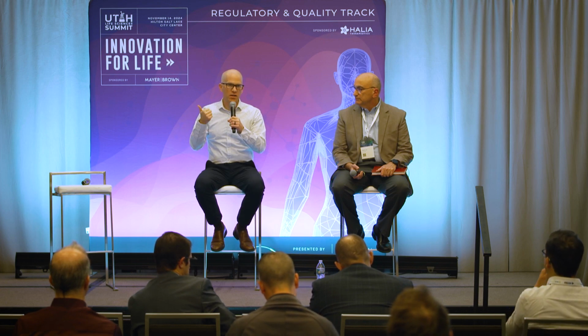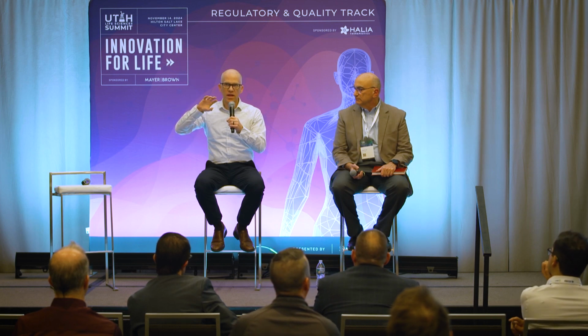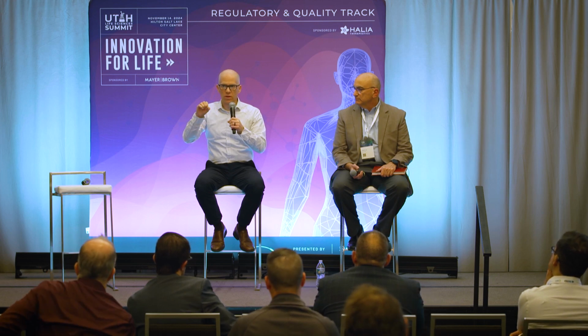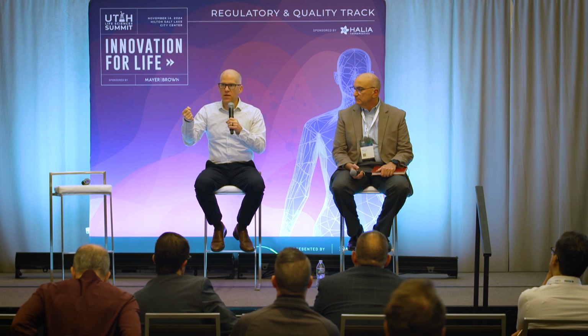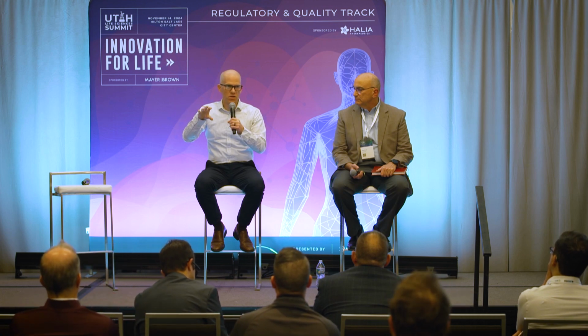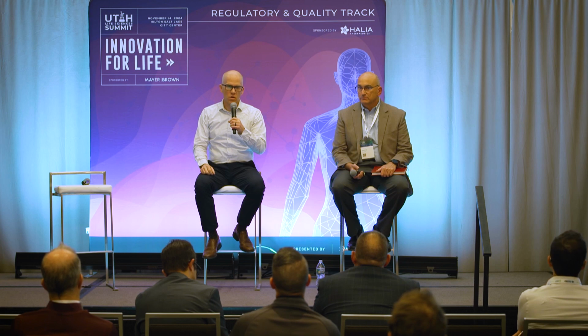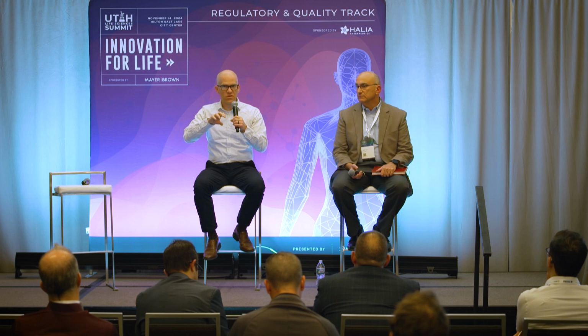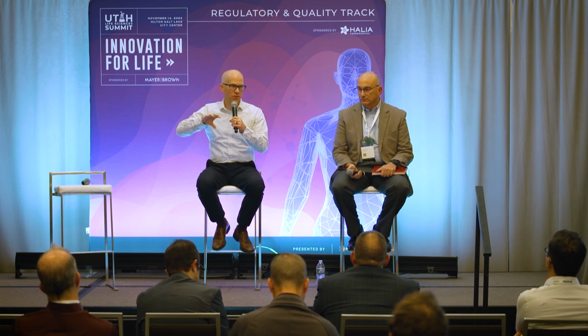And it's important, I think, to separate these out into different buckets, because you're going to tailor your risk controls based on the safety of the information and the impact each of these different assets of the system have against the rest of the ecosystem of the medical device. So with information, you want to talk about your error messages and diagnostic messages of the device, which are different than your personal health information, or any other sensitive information, like maybe a username and password that you have in the system. And so you want to make sure that's separated out as different assets within your cybersecurity risk analysis.